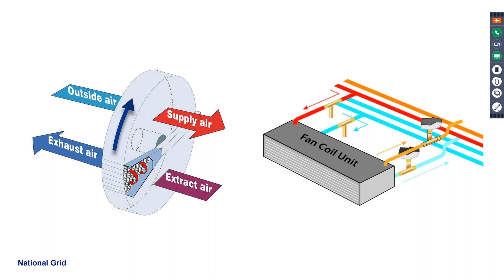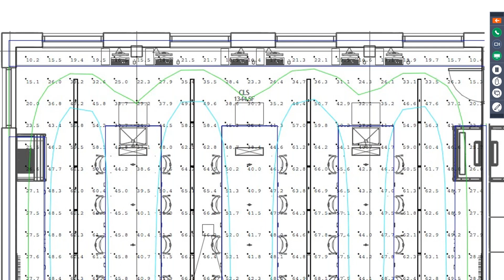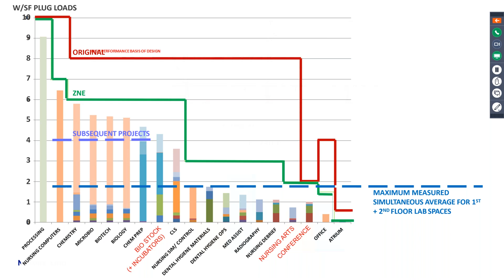We also addressed the lighting power density. We were able to achieve a 0.5 watts per square foot in the lab spaces. And we did a detailed plug load study to right size the systems, which significantly reduced the mechanical cooling loads.